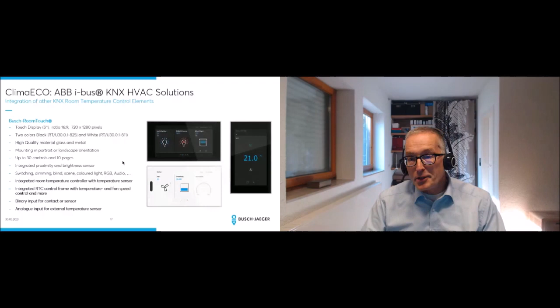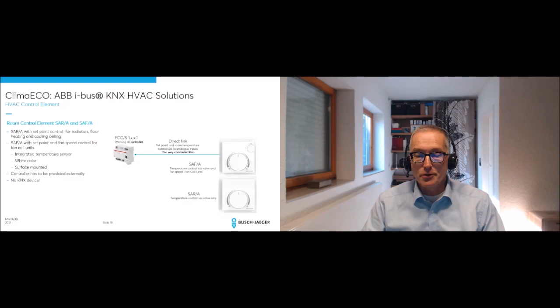So another simple solution to create a room temperature controller is this non-KNX device, room control unit. Just to change the set point, to measure the temperature, of course, and if you have a fan coil unit behind, to change the fan speed if you want - nothing else. You connect it via 4 wires directly to the inputs of this device. You program everything in the fan coil or valve drive controller. It's the same principle, and then you have your complete room solution for room temperature control.